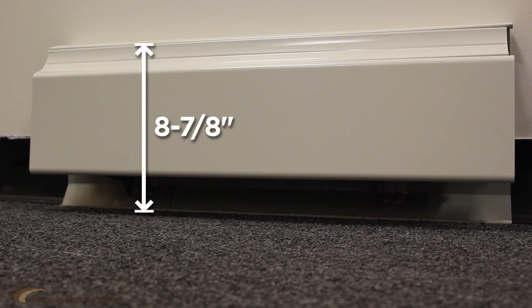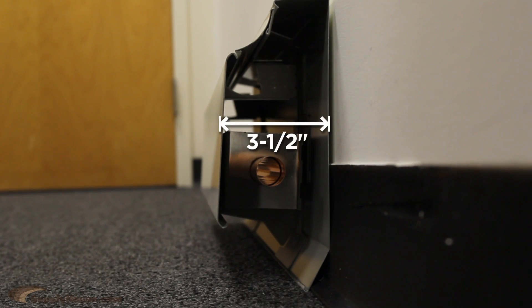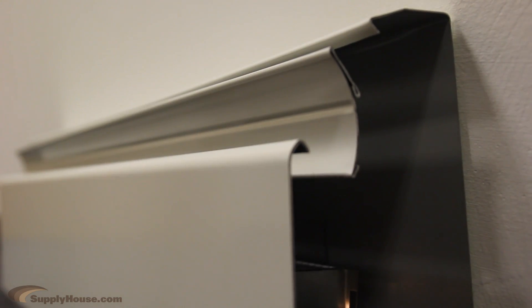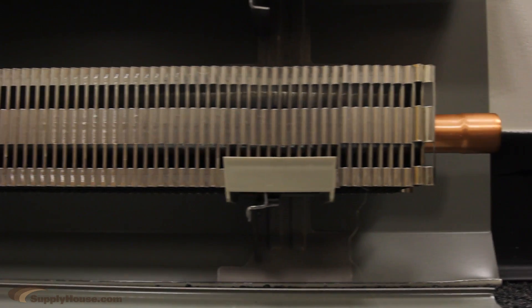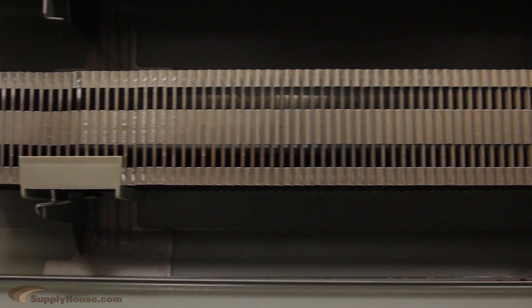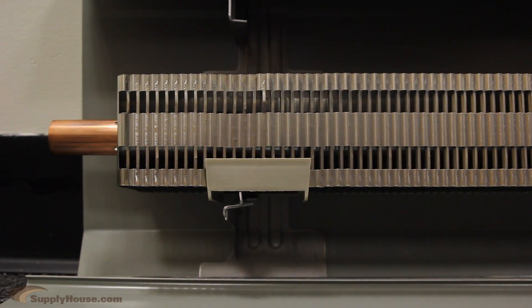The Multipack 80 has an overall height of 8 and 7/8th inches, and an overall depth of 3 and a half inches, with BTU outputs ranging up to 1,030 per foot. The Multipack 80 also offers several different element options for greater pipe sizes, different pipe materials, and different BTU outputs.